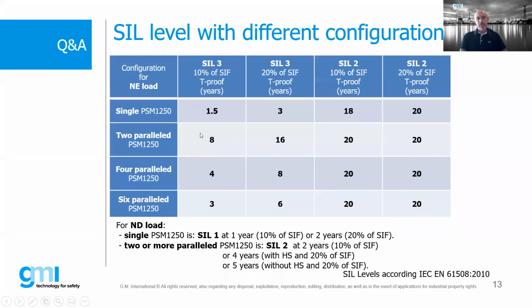So in the same normal energized load, you can use two parallel power supplies. You can extend the proof test interval a lot for the 10% and also for the 20%. Four parallel, again more. For the 10%, the 20% is a little bit lower, and the 6 parallel as well. So this table means that maybe the safety won't be increased so much if I use many more devices in parallel, because if you remember correctly, just one power supply is enough to reach the safety, but of course it increases my availability a lot.